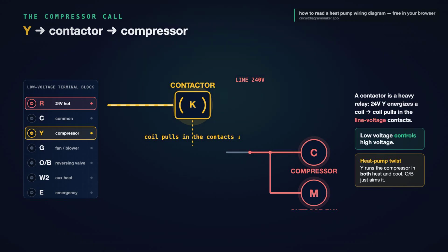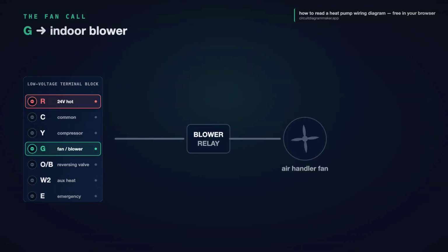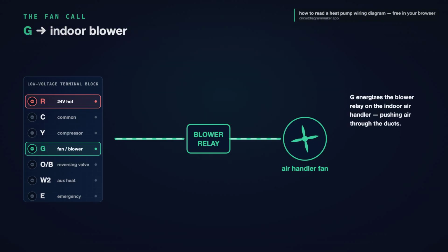Is the reversing valve, that O or B wire, that decides which way the heat flows. Y makes it run, O or B aims it. Then there is G, the fan or indoor blower. Trace G and it energizes the blower relay or the fan control board on the indoor air handler, pushing conditioned air through your ducts. On the diagram, it is usually its own tidy branch off the terminal block.